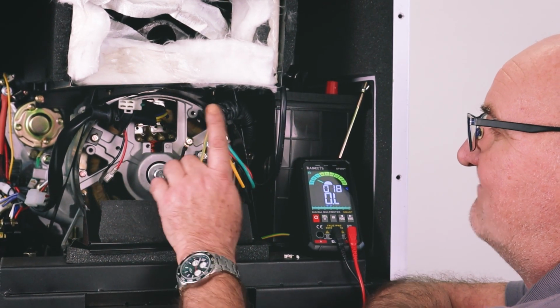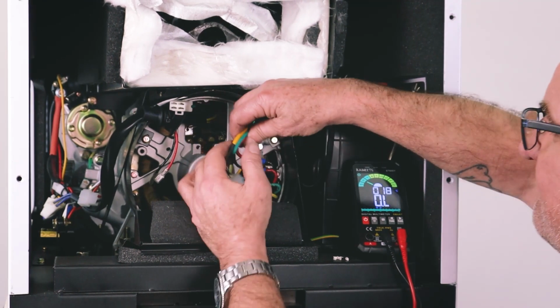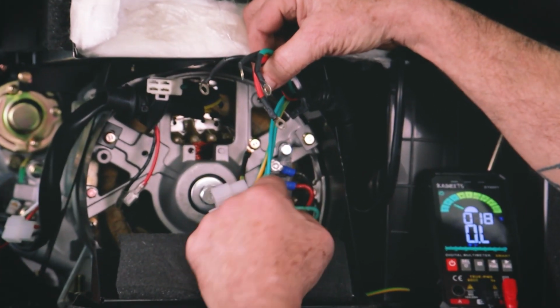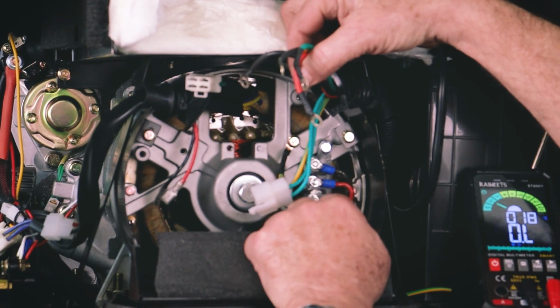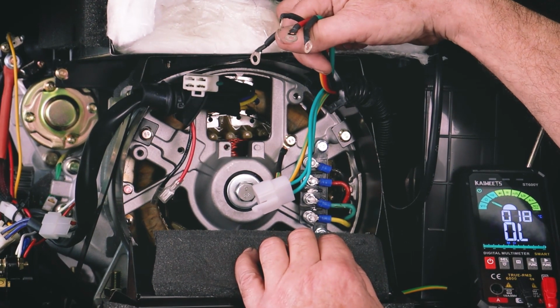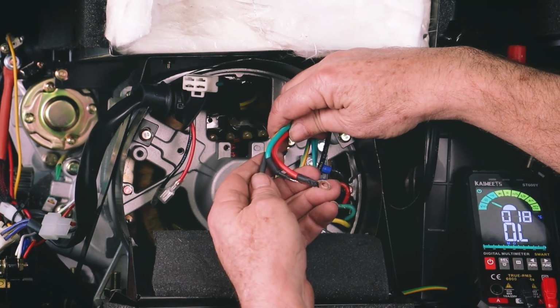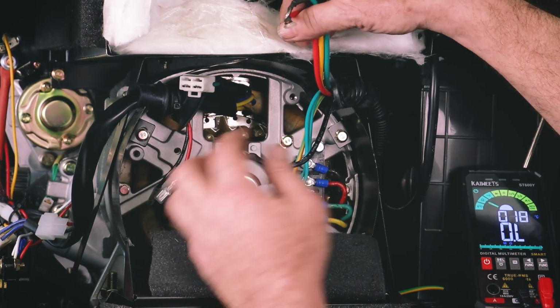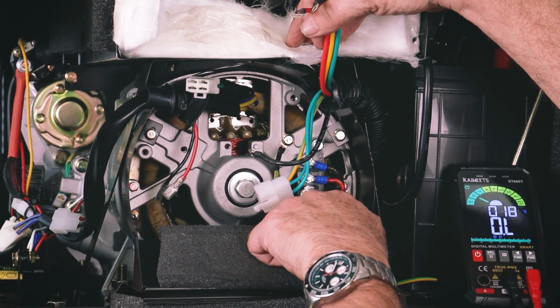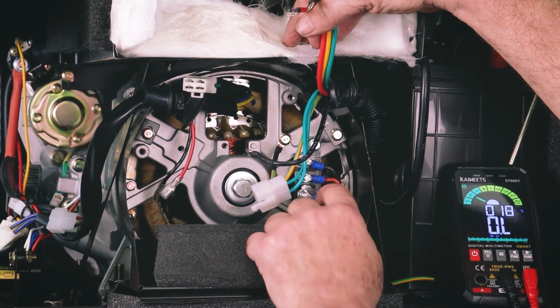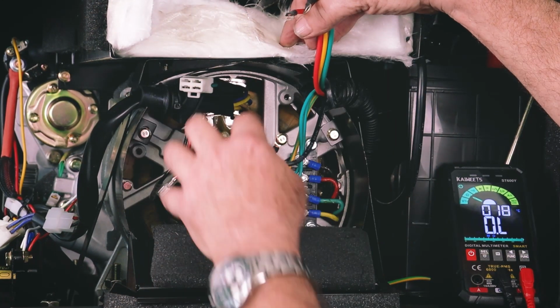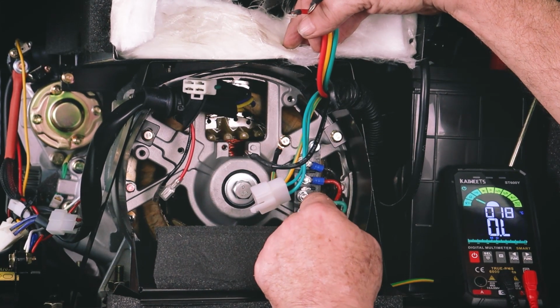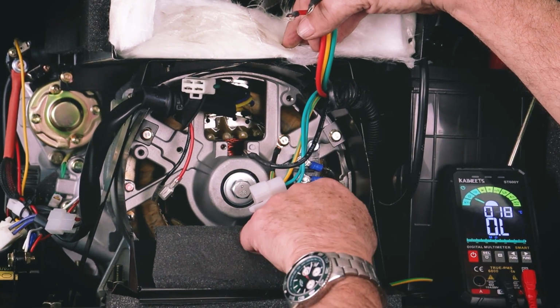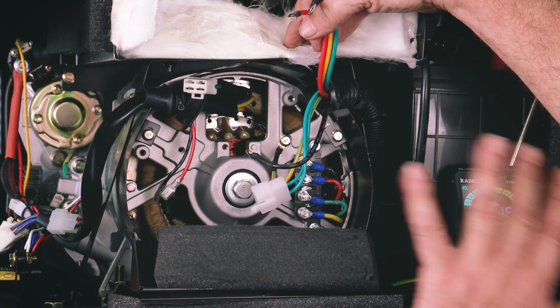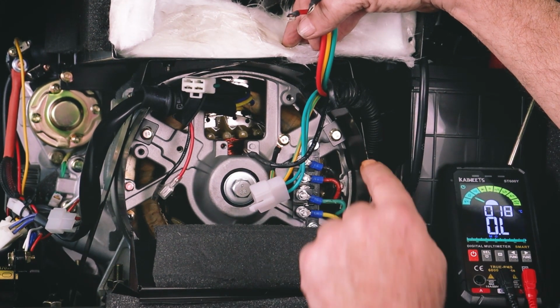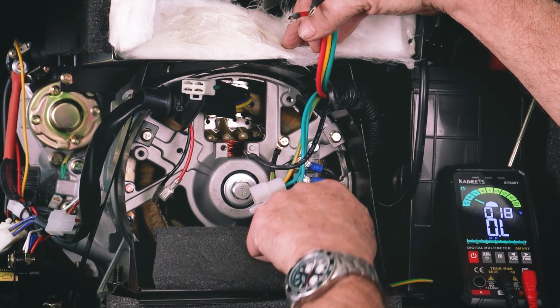One thing I haven't mentioned, if, for instance, we're getting all the correct readings down here with the engine running, we could connect the AVR system back up, not these wires, and then we can probe the voltage across these terminals with the engine running. But again, very dangerous. We've got rotating parts, we've got live electricity. We would be being very careful with our probe, probably a couple of wires with crocodile clips, so we're out of the way when we're testing it, but we would be looking for 110 across there, or 115.